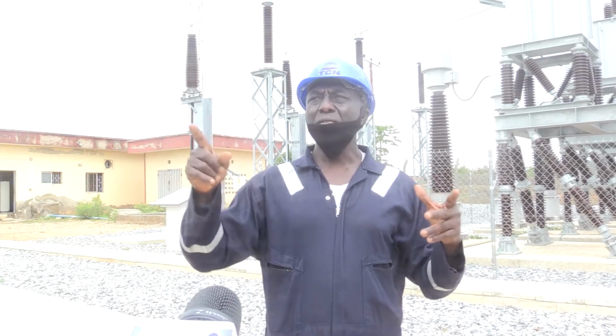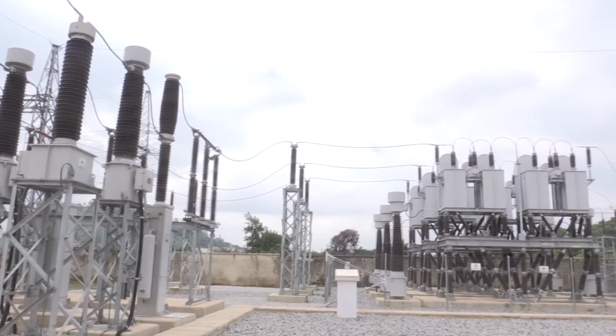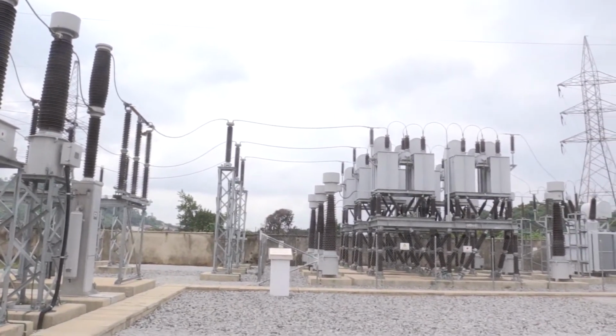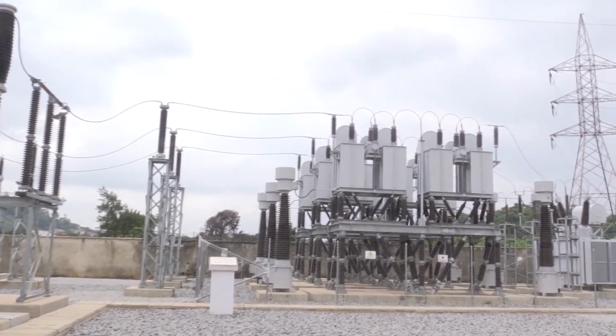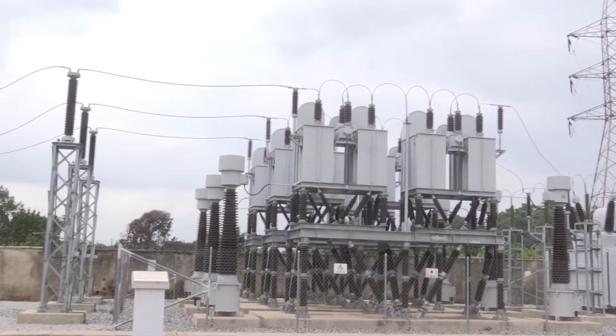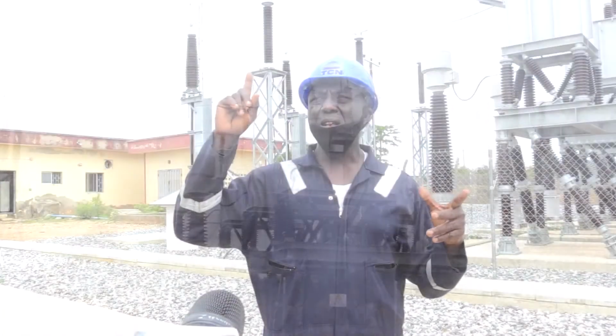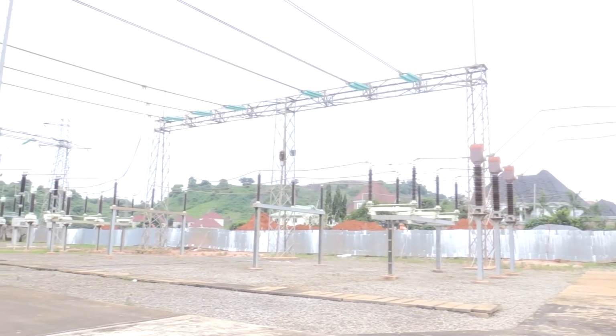Engineer Madugu also explained that the Kefi substation gets bulk power supply from Akwanga and Karu substations on a 132 kV transmission line, necessitating the need for a capacitor bank to boost the voltage level for bulk power supply to its outgoing feeders. With the voltage drop along to Akwanga, it will improve the voltage. To Karu, it will improve the voltage along the 132 kV line, so it will have much effect on the kV outgoing feeders.